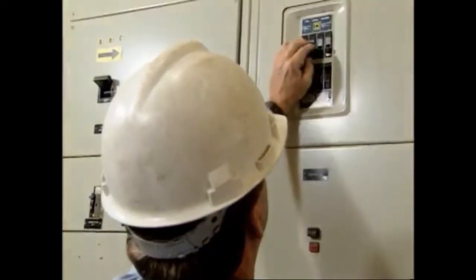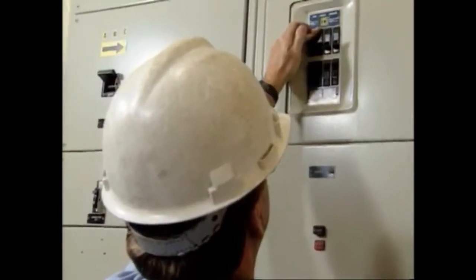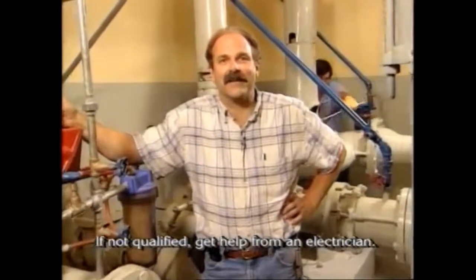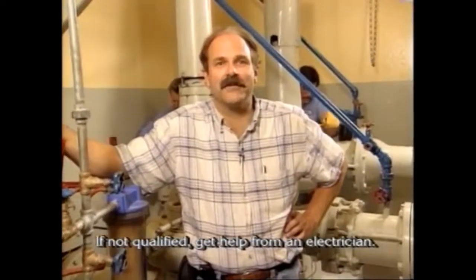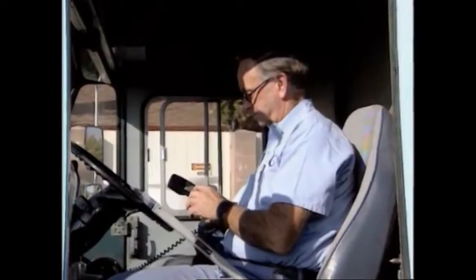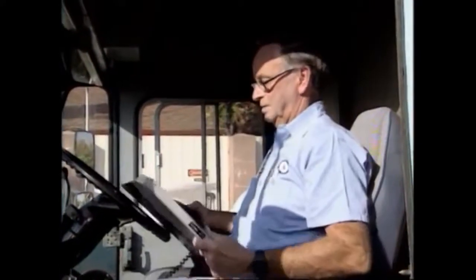Converge on the source of the trouble, mechanical or electrical, motor or motor control, whatever it might be. Electrical problems frequently result from some type of phase imbalance, undervoltage, or high ambient temperature. Pinpoint the problem exactly, its location, and what you need to repair it. Find the cause. What caused the problem? Moisture, wear, poor design, voltage, or overloading? Repair the problem and eliminate it if possible. If the problem is in the switchgear or motor, call an electrician.